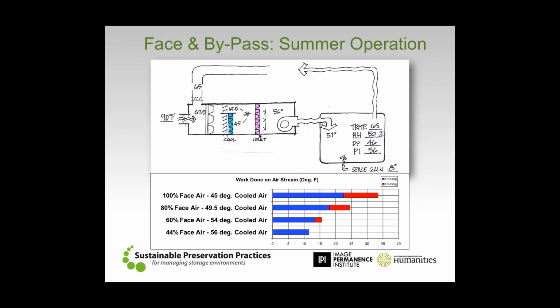We're looking for that sweet spot where the amount of blend or the amount of bypass air is just enough to try and reduce that heating operation as far as possible. Now, there are a couple of tricks in here and there are a couple of catches. The first one is that this really works best when we're not using a lot of outside air, because anytime that we use bypass, we bypass air around the cooling coil. If we have a large quantity of outside air coming into the system, then part of the air is going to go by and never get dehumidified.